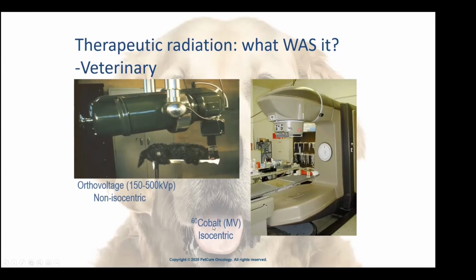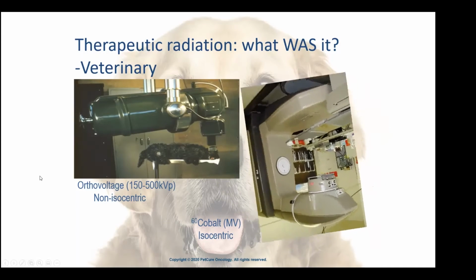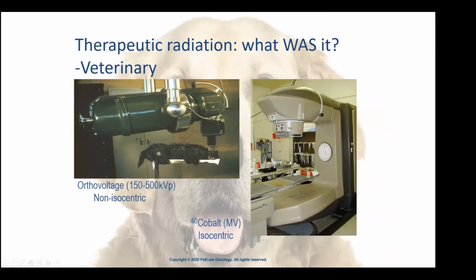Then the advent of cobalt. So this is a radioactive source similar to radium that was up inside a gantry that was isocentric. So now we have a machine that moves around the patient, who's anesthetized and static on the table. The machine moves around what's called an isocenter, and that's the center point of our calibrated machine's highest dose output. We put that at the center of the tumor. We don't have to move the patient. We just simply have the machine move with multiple beams around the patient.